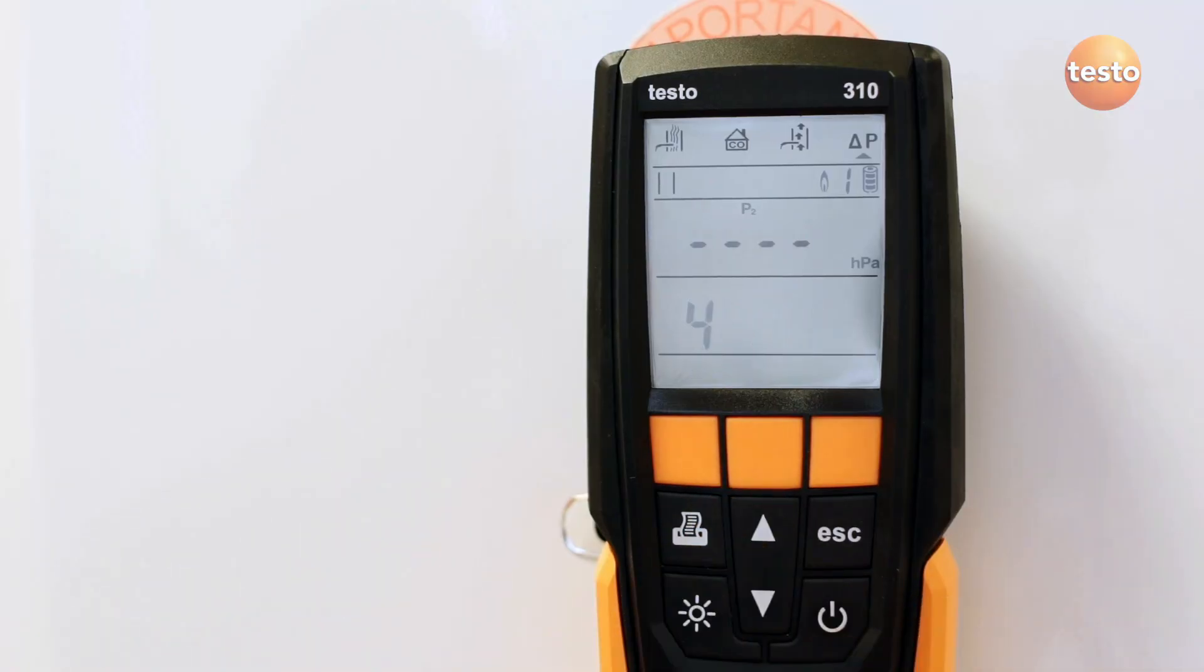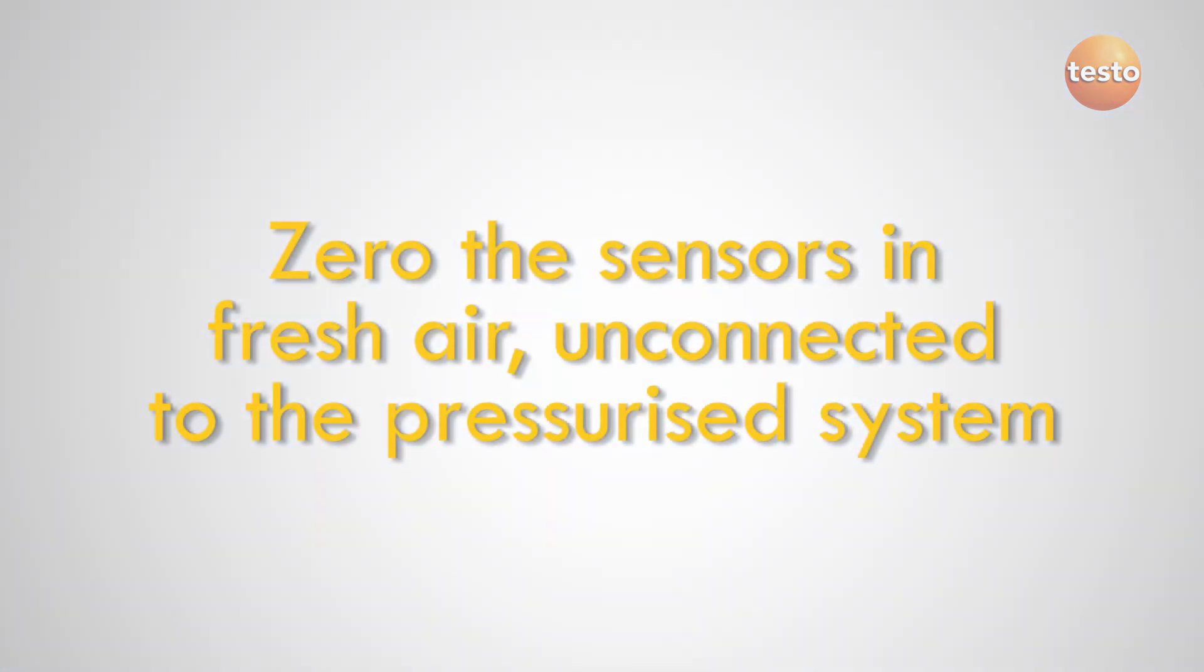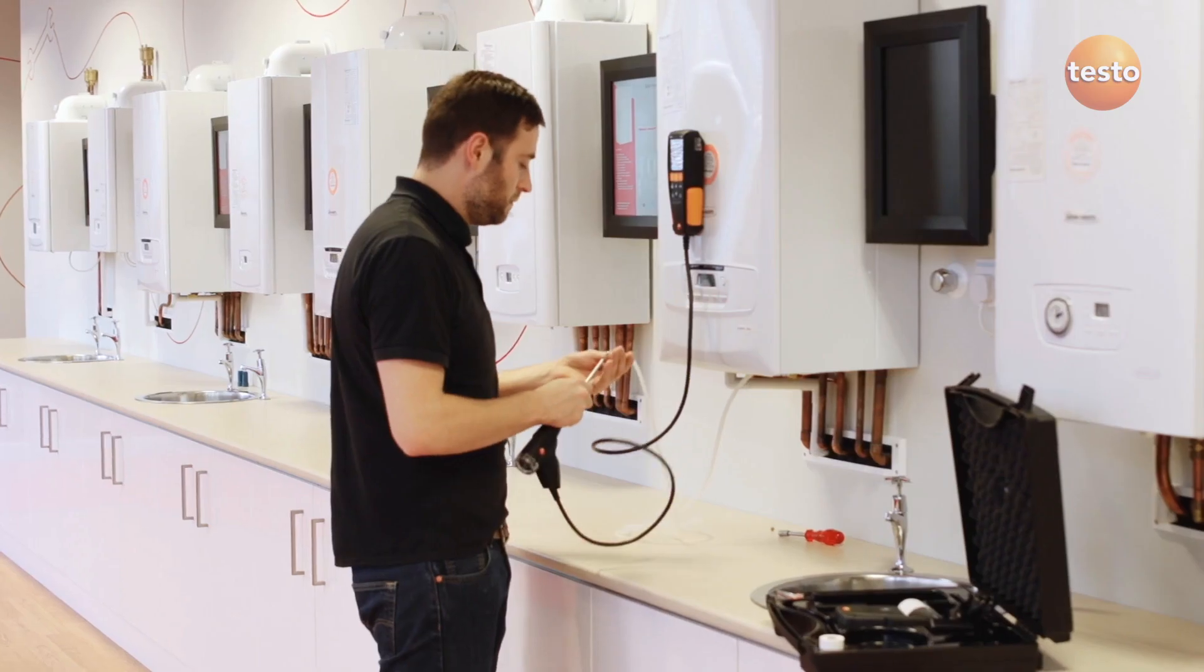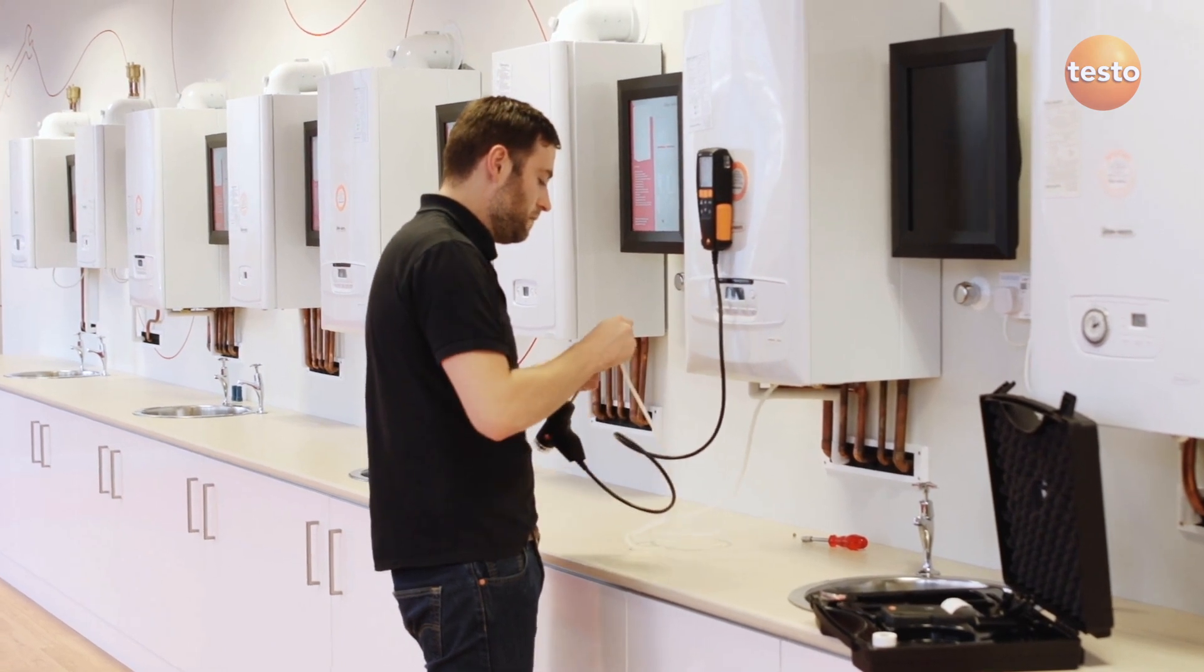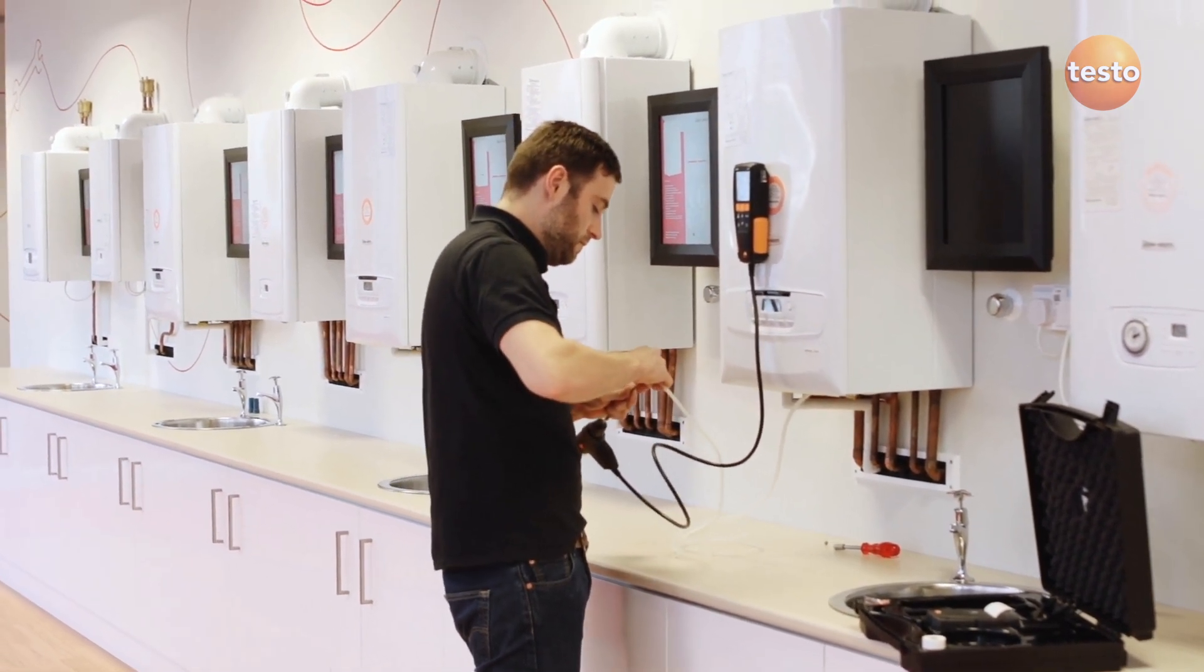Once the plug is in place, press start to zero the pressure sensor before connecting the probe to the gas supply. It's important that the sensors are zeroed in fresh air, not connected to the pressurized system. When the pressure sensor has been zeroed, you can fit the silicon hose to the probe and connect it to the test point to measure the gas pressure.